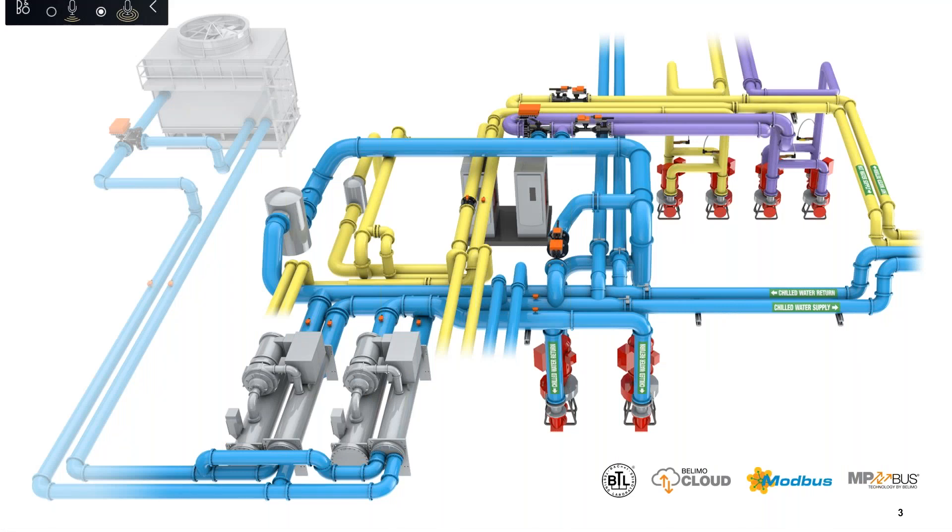At AHR we will display an overview of a hydronic system and how Belimo plays a key role. Hydronic system problems are revealed when building occupants report comfort issues or facilities see an increase in energy usage. Common indicators are spaces too hot in one area and too cold in another, or there are poor system delta T driving energy costs higher. The key to achieving perfect hydronic control is maintaining your design flow at each terminal unit, even if your system pressure changes.